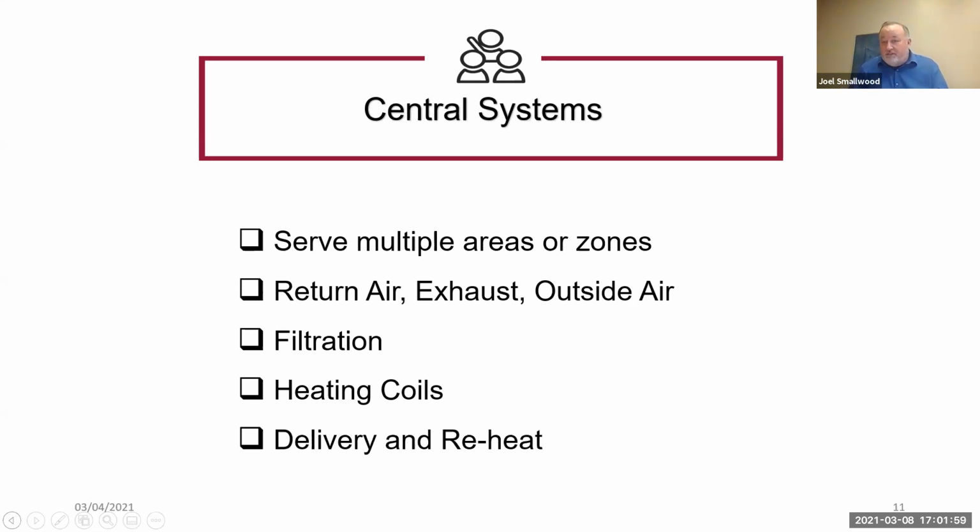Now, one might say, why not bring in all the outside air? The problem with that is the outside air is usually too cold for that, and we can't keep up with it. Our boiler systems and these heat coils that are in here can't keep up. So a room would just continue to get colder and colder as the day went along. The harder it worked, the colder it would get.